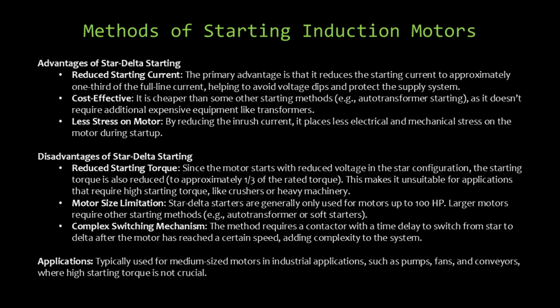Star-delta starting brings significant advantages to motor operation. The method dramatically reduces starting current to approximately 1/3 of full-line current, protecting the supply system from voltage dips. It's more cost-effective compared to some alternative starting methods and places less electrical and mechanical stress on the motor. For many industrial applications, this starting method offers an optimal balance of performance and protection.